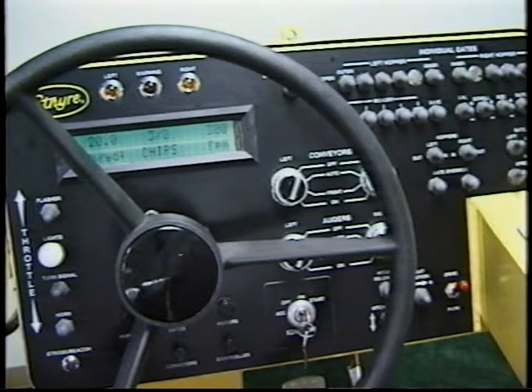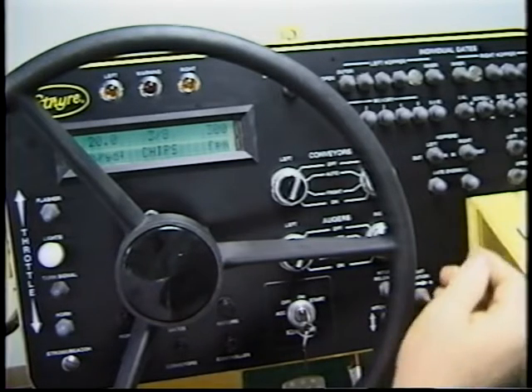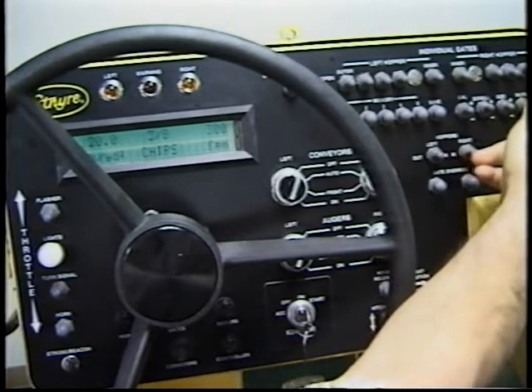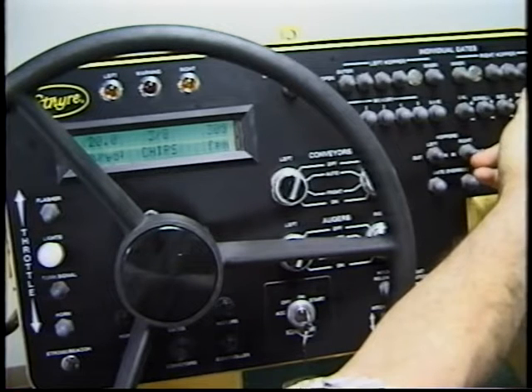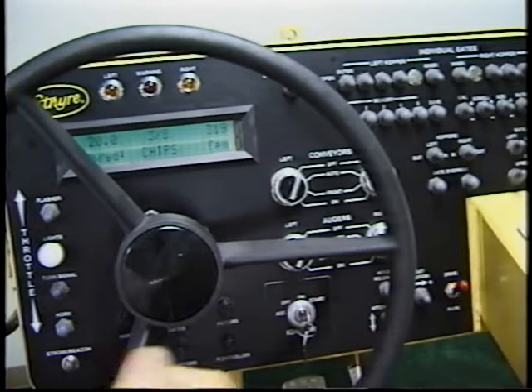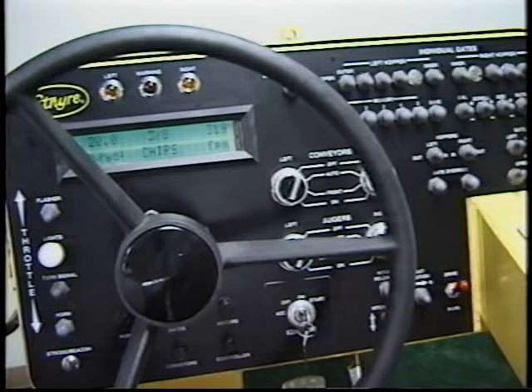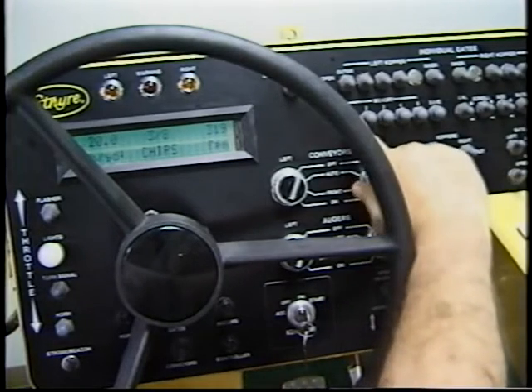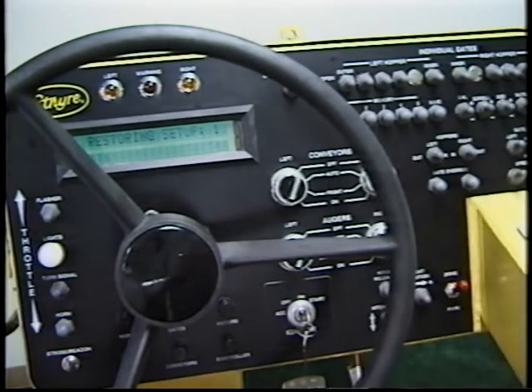It is important to understand that the memory functions simply restore the selected values to the operator screen. If one of the values is changed while operating, such as the speed set point, the speed will change. The value stored in the memory will not change. Pressing the memory push button will restore the saved values and override the changed speed set point.